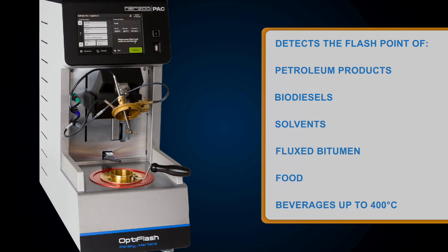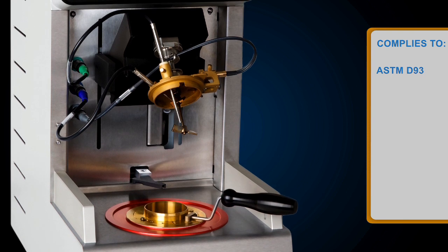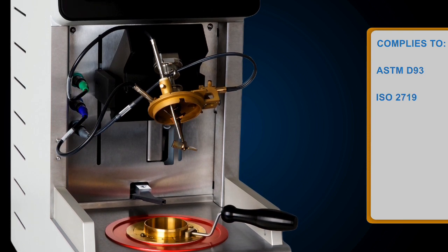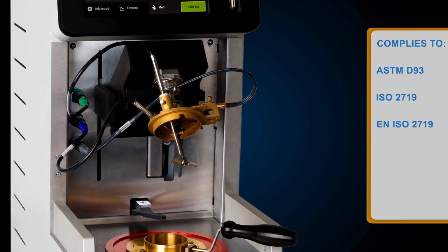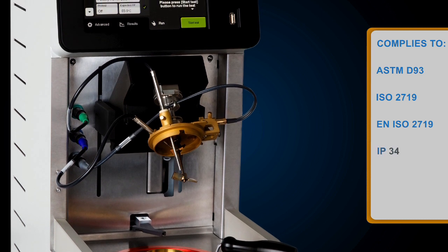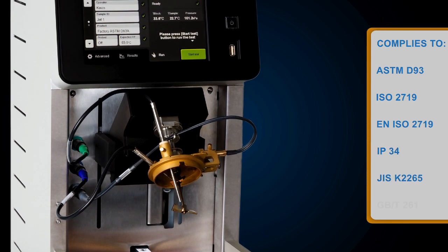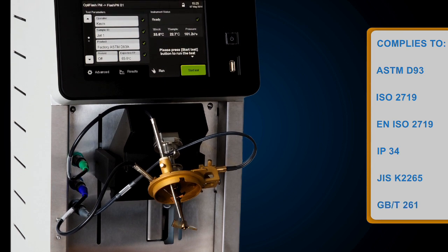Food and beverages up to 400 degrees Celsius. It complies with leading global standards such as ASTM D93, ISO 2719, EN ISO 2719, IP34, JIS K2265 and GB/T 261.